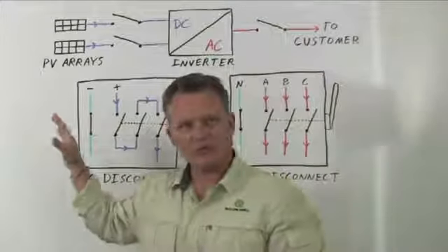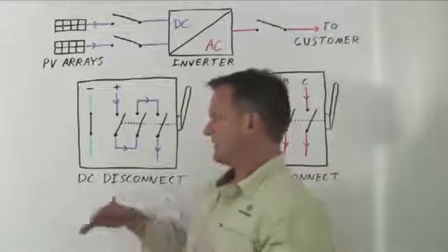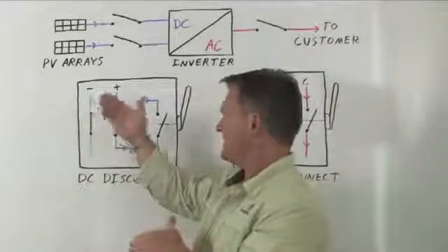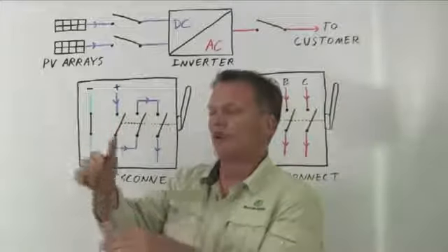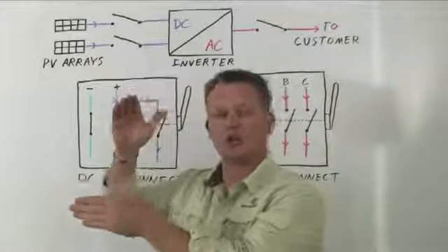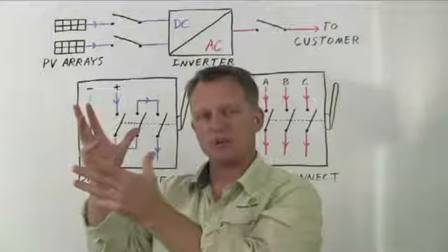That's not the case with DC current. Now, with DC current, it's a constant value and it stays persistent. When you open up a DC disconnect switch, an arc forms and it wants to continue, and you have to open it with even a larger air gap to get it to extinguish.